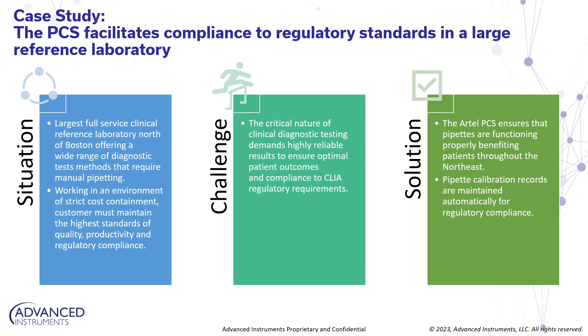In addition to those systems, the MVS and the PCS, there are services that employ the same technology. In the case of these services, laboratories that have strict regulatory requirements and/or minimal staffing to allocate to quality control methods will choose these services. The specialists that perform these services will use the MVS to perform volume measurements on all your critical liquid handlers to avoid downtime and help you stay on schedule. They can keep your workflows moving forward by ensuring that your automated liquid handlers dispense the correct volume.